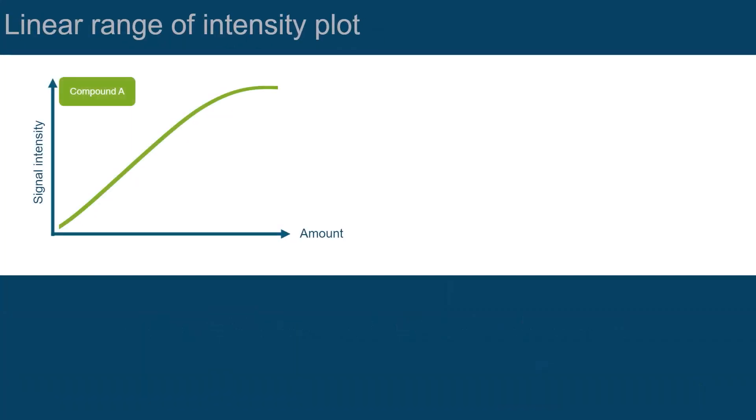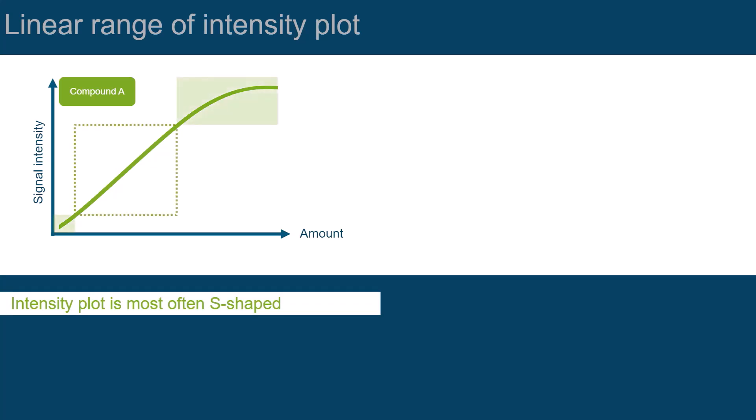Before we move on with the discussion of calibration curves, let's have a closer look into the intensity plot. Most often, it is S-shaped. We can define three different ranges. At lower amounts, it usually has a flattened slope. With increasing amounts, it becomes linear before it starts to run into saturation at high amounts.